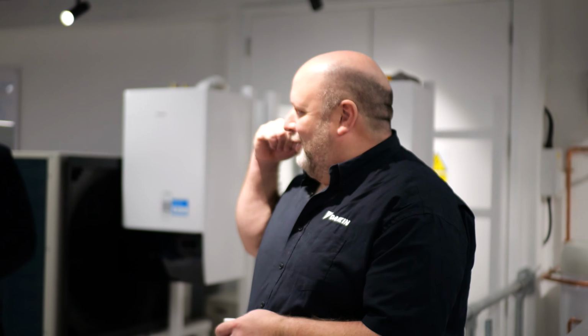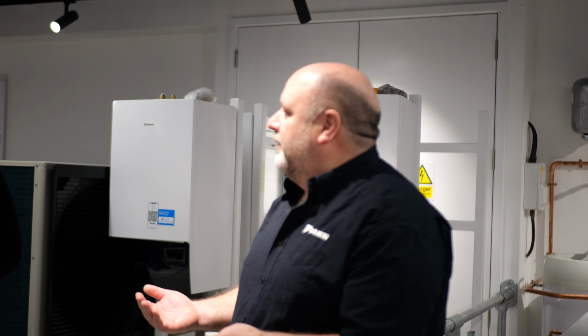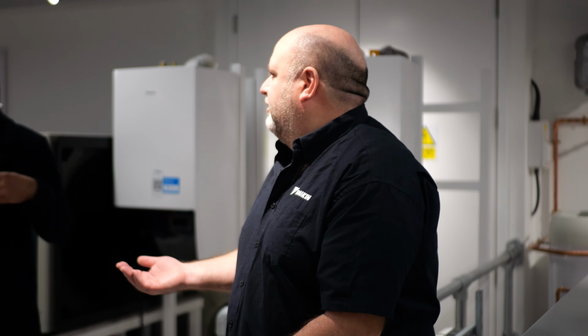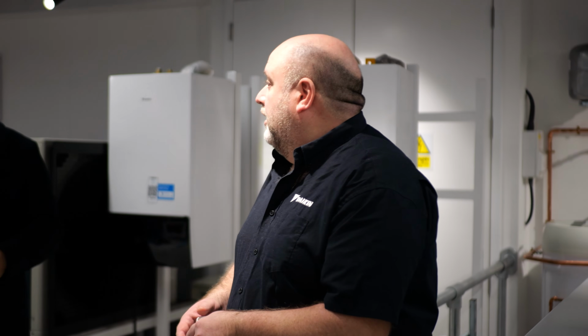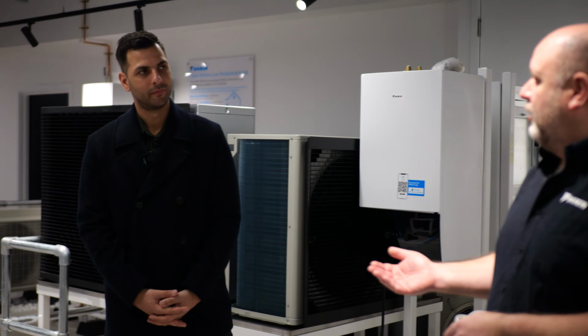Interesting conversation is backup heaters. We talked about outside out, but the other reason for a backup heater is to give you some capacity when you've got a bit of a shortfall. So quite often you'll find it's more energy efficient to tightly size the heat pump at the lower end, and maybe the heat pump won't get to the very cold conditions - it might be 10 hours a year, 20 hours a year. It could be more energy efficient to run that electrical heater for 20 hours a year and have the heat pump be able to get down to a much lower load - a smaller heat pump.